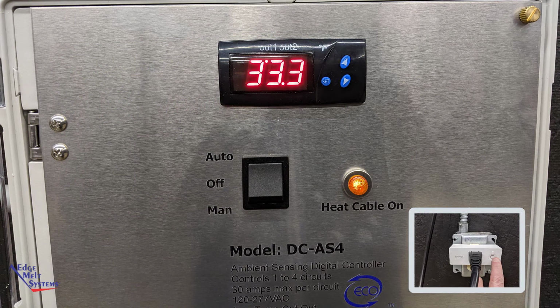When operating via a smart switch or smart outlet, the control panel itself is left in the auto position, and then the smart outlet can be used to turn the control circuit on and off. When the control circuit is on, the panel will function normally in its auto setting.